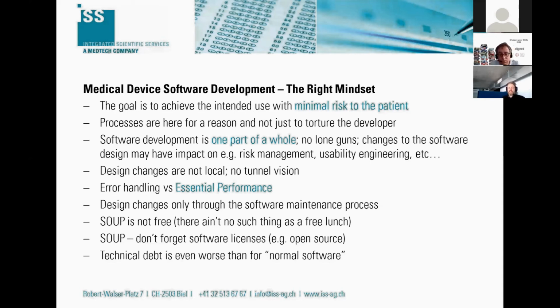Also important part is that SOUP is not free. There are a lot of shiny, sexy frameworks and component libraries out there, but each one incurs a cost in the maintenance, in the vigilance, and so. Also, SOUP usually comes with a license, software license, especially for open source. So be aware that you need to check the license and make sure it's compatible with what you're writing. Not that your whole medical product suddenly has to become open source.